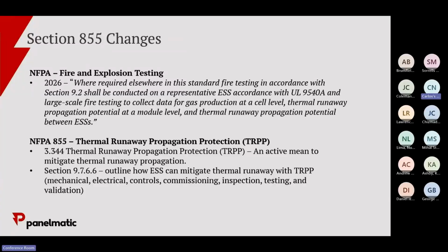So then the thought was, okay, use water. But once these things start going up and into runaway, water's not going to help. What ended up happening is they would dump water on these and seal the enclosure, which would somewhat contain it, but once the event was done and you opened the doors, you'd have a whole bunch of toxic water running out onto the floor. So they started using a Novec system that would spray a gas to eliminate oxygen and hydrogen and try to prevent and contain the event that way.